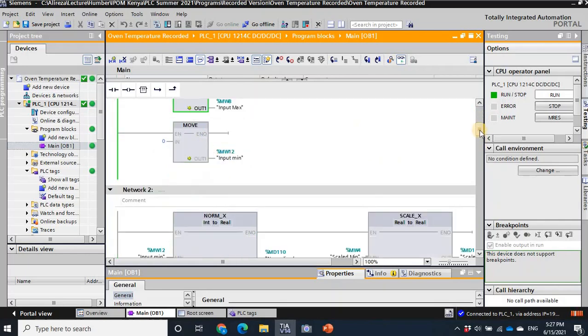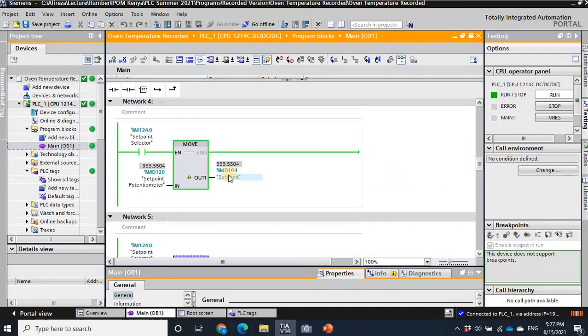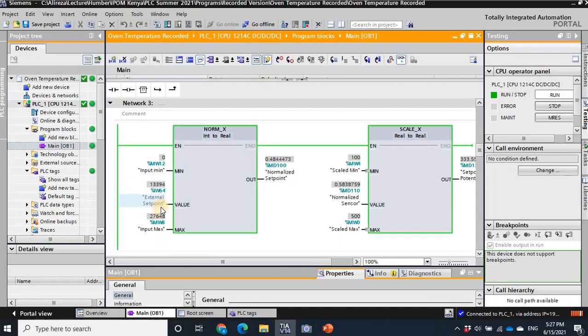Let's find the set point — this is the set point. We expect that when we are in external mode and we change this, it should change, but nothing changes. This is the set point that should change from the potentiometer. Here is the external set point — when I change the potentiometer, this external set point value changes, so the input is correctly given to the PLC. The problem is somewhere in our program's calculation.